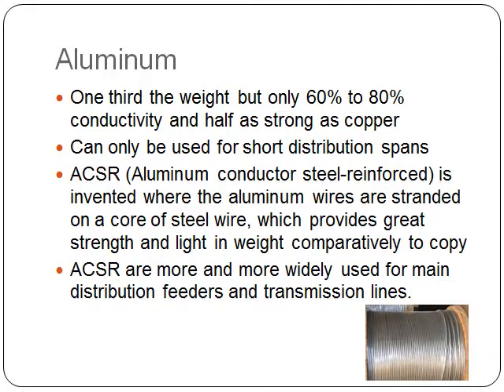Aluminum is one-third the weight, but only 60–80% conductivity, and half as strong as copper. Because of its strength limitations, it can only be used for short distribution spans. There is another technology called ACSR — Aluminum Conductor Steel Reinforced — where aluminum wires are stranded on a core of steel wire, which provides greater strength and is comparatively light in weight compared to copper.